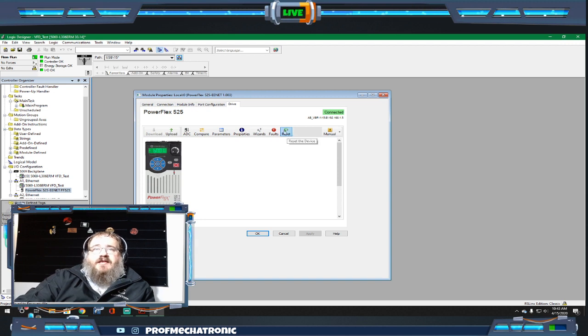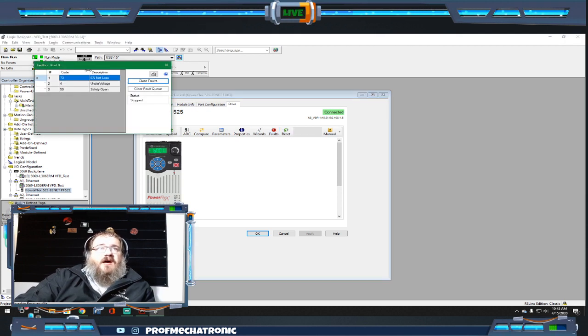We'll work our way back. Reset's pretty self-obvious. Faults, you can see the last faults, right? These were the last faults that were on there. We had a safety open, under voltage because I powered it down, and an ENET loss because we were configuring those different IP addresses. So that's really important to see those previous faults.